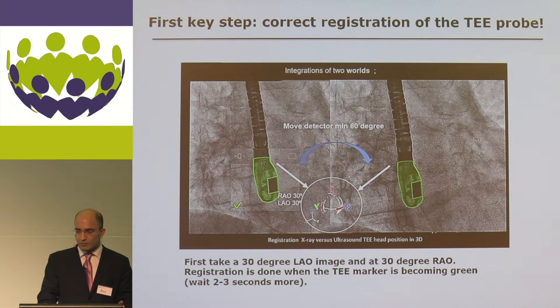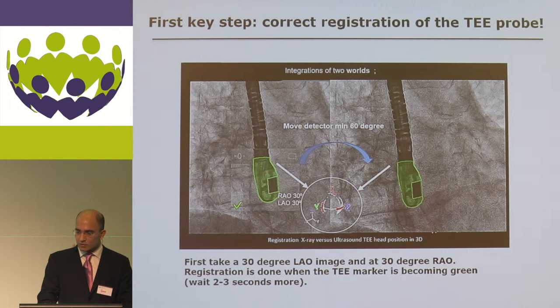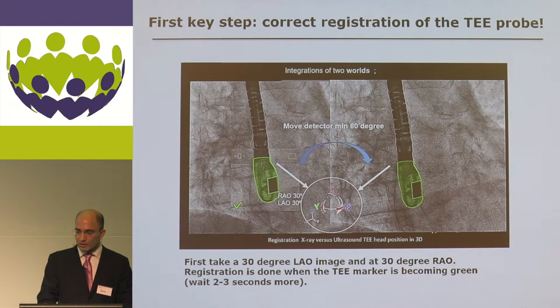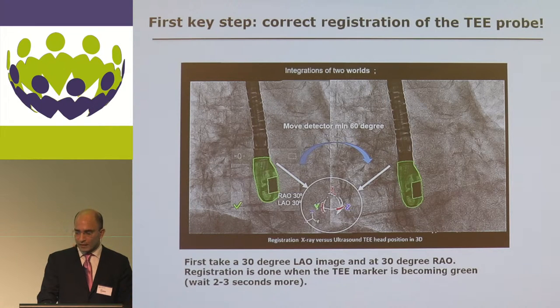The first step when using this technology is to perform correct registration of the TEE probe. This is very easy — you take two orthogonal views and the system will localize and track the TEE probe, which will appear as a green spot on the TEE marker. You need two orthogonal views with at least a 60-degree difference.